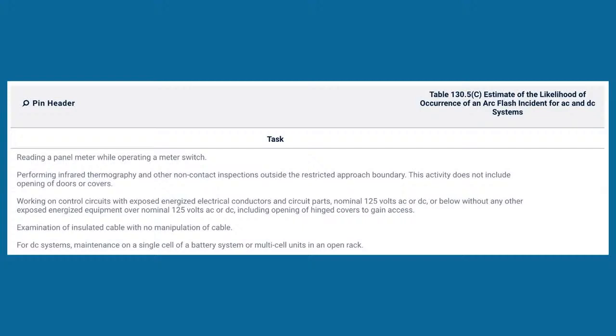Now, let me give you an example. When we first started doing this, and I would be out teaching this, somebody would say, well, what if I'm doing a scan on a transformer, the transformer could be up in the ceiling, I don't have clearances and stuff up there. And I said, that's perfectly fine. What you need to do is go upstream, turn it off, and lock and tag it out, and then make sure everything's de-energized: test the meter, test the circuit, test the meter again. And then you need to set stuff up to where you've got protection from anything that could create a touch and step potential. Once that happens, you can go up there and turn it back on. You've got all your protection techniques in, and now you can do that thermography scan on that transformer.